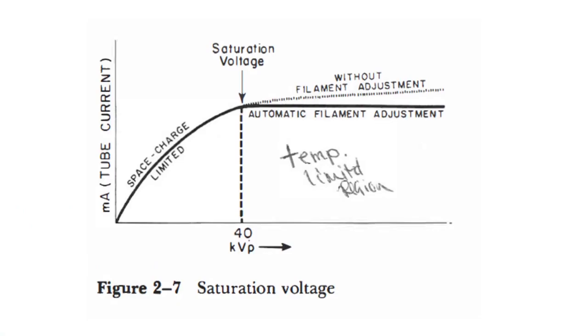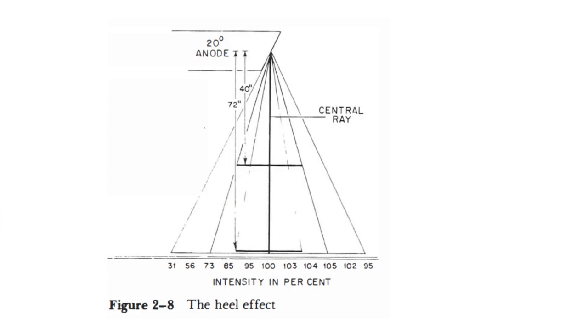Hello friends, let us now learn about the Heel effect. What is the Heel effect? See, the intensity of the X-ray beam which leaves the X-ray tube is not uniform. The X-rays which are produced do not have the same intensity.